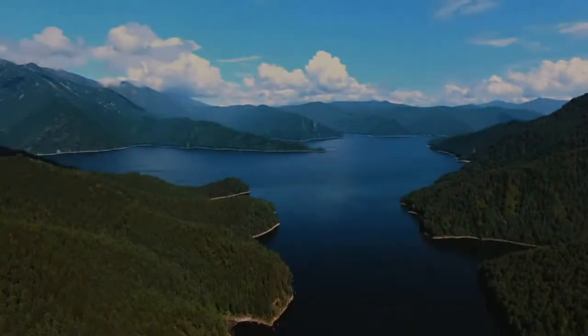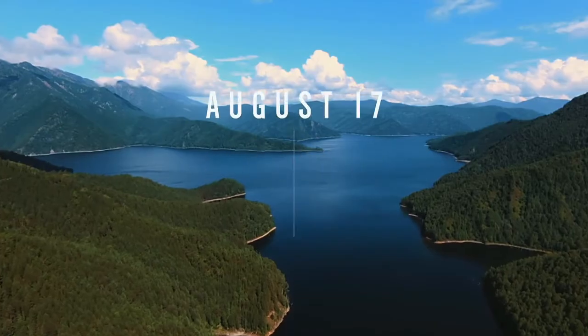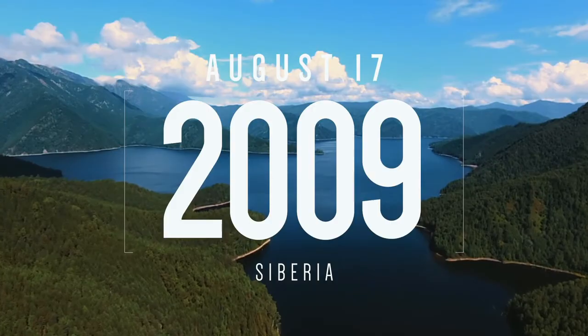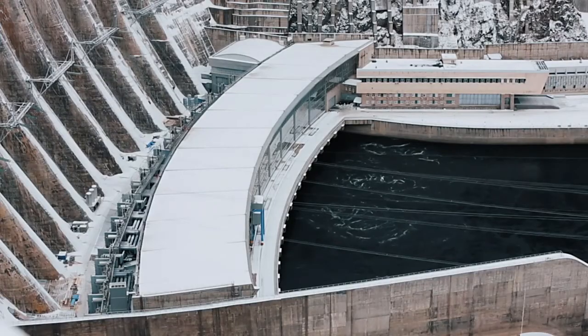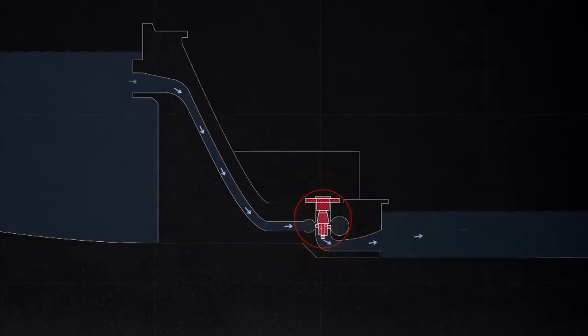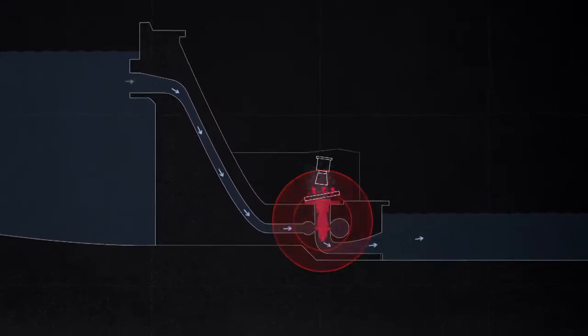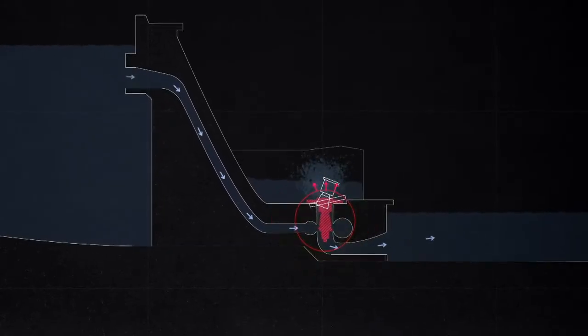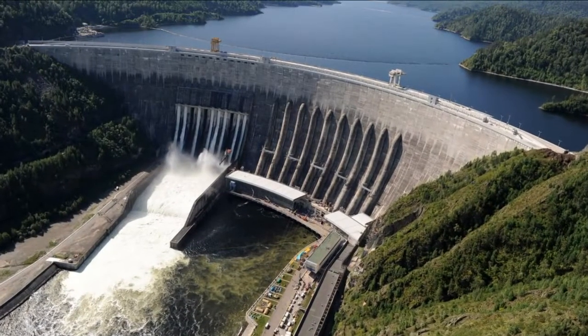Just a few hours later, at 8:13 AM, Unit 2 experienced a load rejection, which was followed immediately by a loud bang heard in the control building adjacent to the powerhouse. Unit 2 essentially ejected 1,900 tons of steel into the air, allowing a jet of water to shoot straight up through the roof of the power facility. Seconds after the geyser blew off the roof, another very loud bang was heard downstream from the powerhouse.